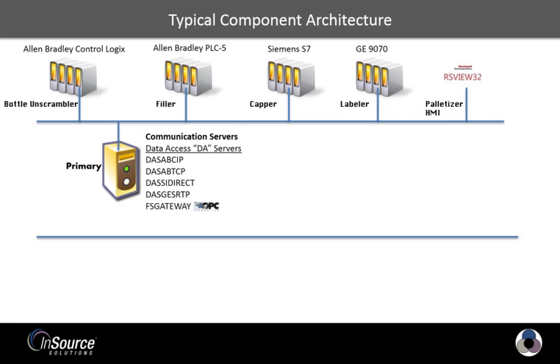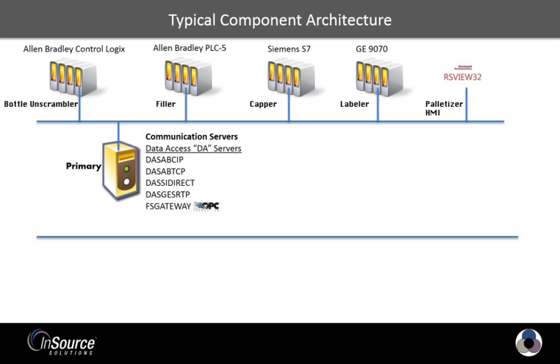The first step is to establish a communications channel to these PLCs so that your Wonderware applications have a data source. Wonderware provides software modules historically known as drivers or IO servers, and the next generation of these modules are called data access or DA servers. These modules reside on a PC or virtual server and act as an interpreter between the PLC and other Wonderware applications like InTouch. Because each PLC communicates via a proprietary protocol, a specific DA server is required for each PLC type on the network. For example, the ControlLogix requires the DAS ABCIP DA server. The Siemens S7 requires the DAS SI Direct DA server and so on.